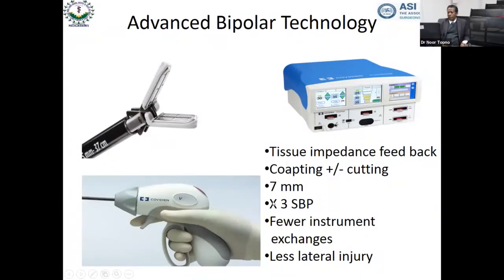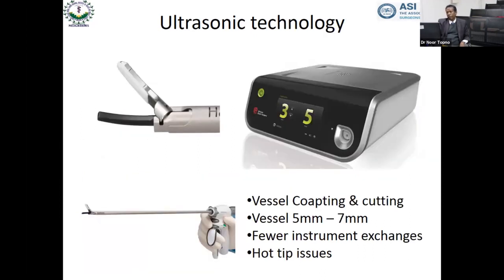The advanced bipolar technology: here basically, the first thing that the machine does is sense the impedance. And here what happens is a process called coaptation. It is not exactly called coagulation, but coaptation. Some amount of pressure has to be used on the tissues which you want to coagulate. And vessels up to almost 7 mm can be safely blocked off by this process. And it can take pressure almost up to 3 times the systolic BP. And lateral tissue damage is considered to be much less. And the system automatically senses that the coagulation is complete and switches off automatically.